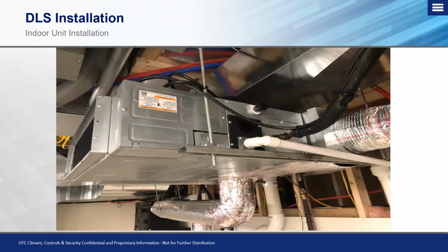Now with the ducted unit, this is an application that I wanted to bring up on here to make sure that we don't run into the circumstance again. So this unit was installed upside down. Now there's a few different ways that you can tell that. First is going to be, look at where the hangers are. So these hangers are not meant to rest, in this case, on the unistrut. These actually need to be on the opposite side so that they can properly suspend the unit. So that's going to be the first giveaway, is looking, are the arms of the hangers off if you're on the bottom side? If they're on the bottom, the unit's upside down. They need to be up at the top.